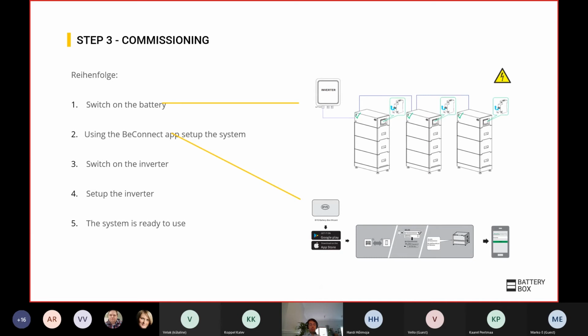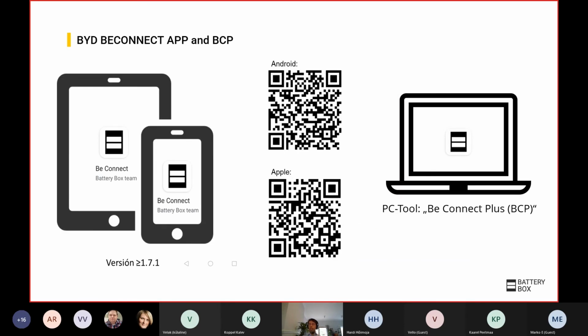So very important, the inverter must be off. Always the inverter must be off. First thing, you switch on the battery, then use the BeConnect app to connect to the battery and do the commissioning. And then once the commissioning has been successful and you see a white light in the LED, then you can switch on the inverter and do the commissioning of the inverter. In order to do the commissioning of the battery, you can use both the mobile phone app, which is available in Android and iOS, or you can use the PC tool, which is the BeConnect Plus, that can be downloaded from both the BYD Battery-Box and from the EFT Systems website.